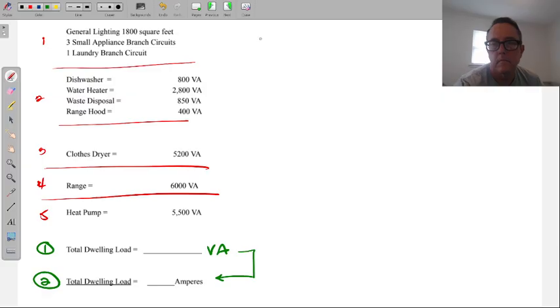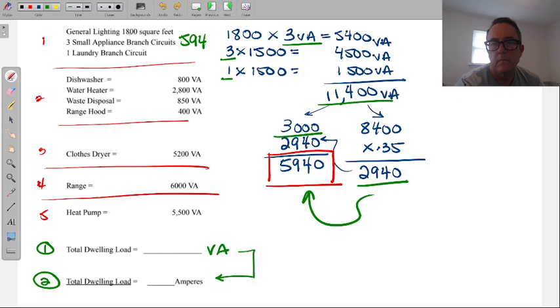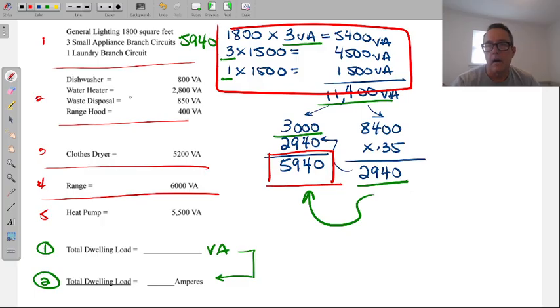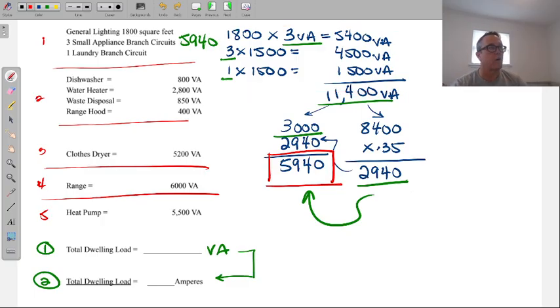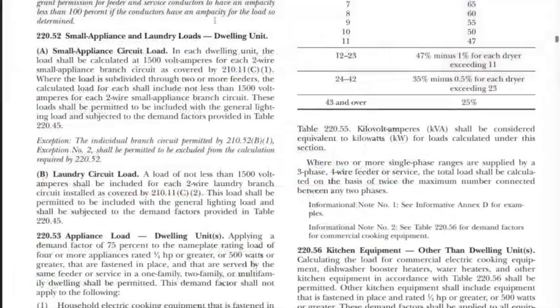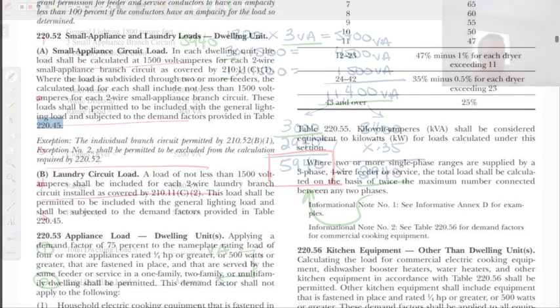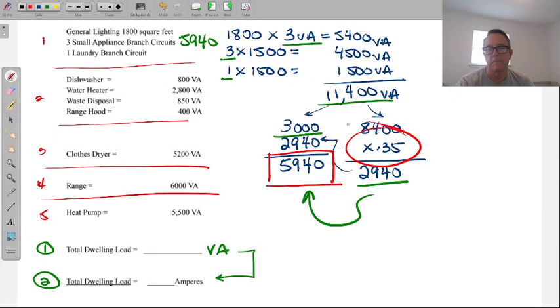Why are you adding the 3 small appliances and the laundry branch circuit to the lighting circuit? Why are we doing the process this way? Yeah, why add them all together? So in the small appliance article and the laundry load article, this note here, starting at these, and this note here, starting at this load, allows us to do that. These loads shall be permitted to be included with the general lighting load and subjected to the demand factor on that table. Table 220.45 is the table that gives us the 35%.